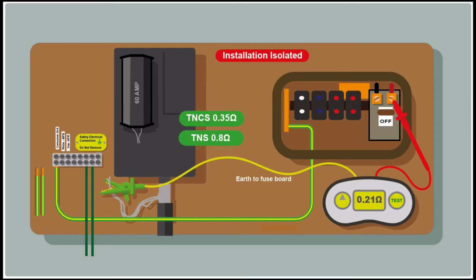Right, I've had a good tidy up of the earthing system. I've got rid of the old nut and bolt MET, installed an 8-way earth block. I've reconnected the old bonding conductors, and I've run a new connection from the MET to the earth bar in the fuse board, and I've got rid of the old earth connection that went back to the old nut. So I've got everything in place for when I want to connect everything back together again. The last thing I need to connect up is my main earthing conductor to the MET, but I don't want to do that until I've done my test because I don't want any parallel paths.